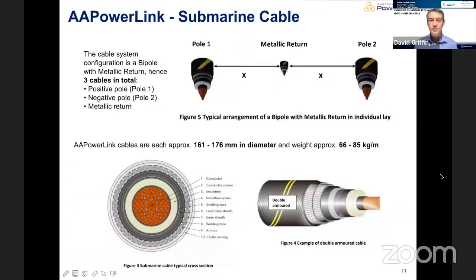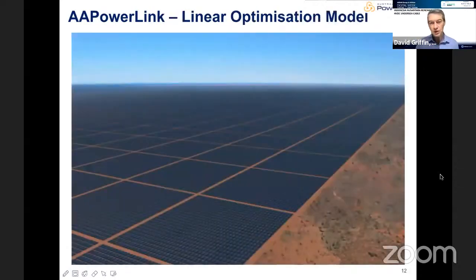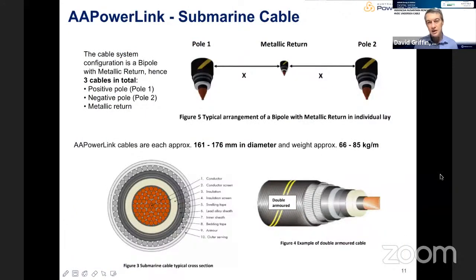The submarine cables are really at the core of what makes the Australia-ASEAN Power Link work. These cables are not a revolutionary technology - the first system was installed back in the 1950s in Sweden, and it's been relentlessly evolving ever since. This was the trigger for founding Sun Cable at the start of 2018: I looked at the technology and determined it had evolved enough that we could now transmit electricity over extremely long distances and through extreme depths of water.